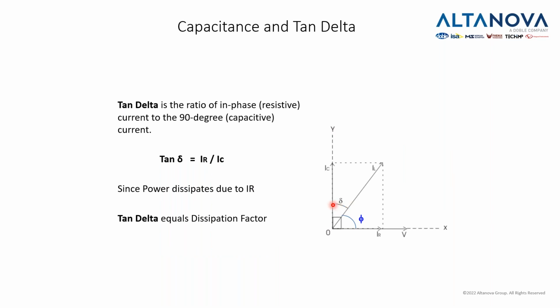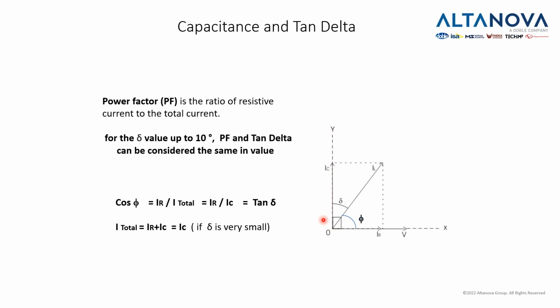This angle, if it's bigger than about 0.7 degrees, more or less, we have a problem with our insulation, which leads you to believe that this is very much like a capacitor. So tan delta is IR over IC. Tan delta is also known as dissipation factor.